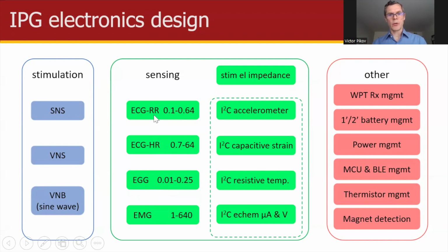For EKG, by the way, we have 2 types of recording. One is to record respiratory rate, and another is heart rate. These numbers here represent the filter settings for low pass and high pass filtering. So together, they represent a band pass filter. And of course, there is a different gain for these channels as well. In addition, we have sensing for electrical impedance from the stimulation electrodes, the ones here on the left.